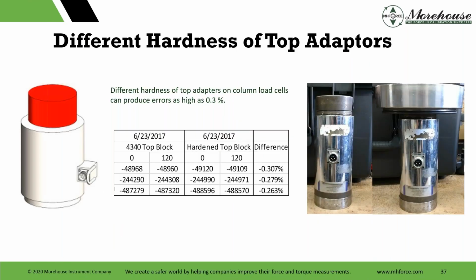This one's a little more repeatable: different hardness of top adapters on load cells. Not all load cells are designed and built the same way. These are multi-column cells. Actually, the one to the right is a single column cell. The one to the left is a multi-column cell. And that's just what it means. It means there's one element in the one to the right, and in the one to the left, there's 4 elements with a lot of strain gauges. These cells inherently, depending on what you use on the top of them, produce a different output.